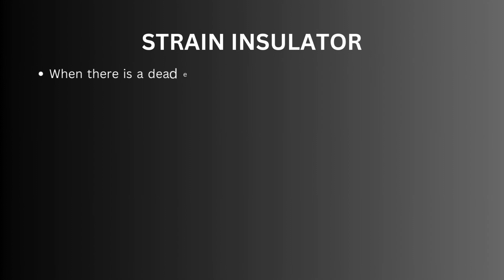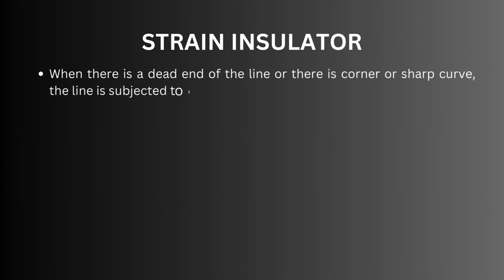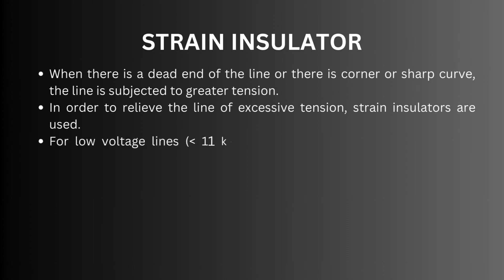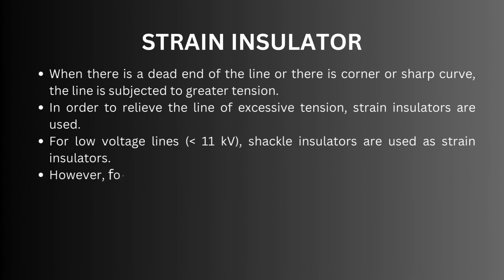Strain insulator: when there is a dead end of the line or there is a corner or sharp curve, the line is subjected to greater tension. In order to relieve the line of excessive tension, strain insulators are used. For low voltage lines less than 11 kilovolts, shackle insulators are used as strain insulators.